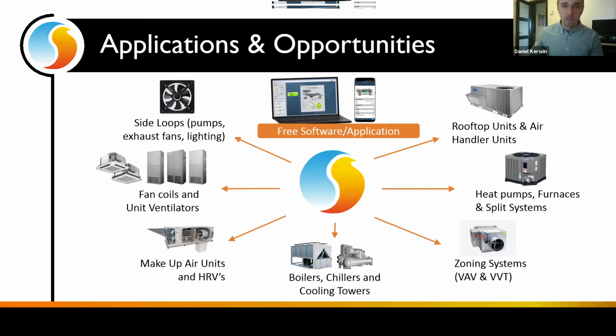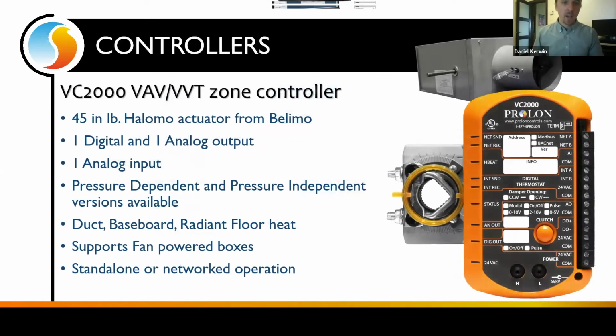So just to go over a few of these controllers. On the zoning side of things, we have a VAV controller right here, which has an embedded Belimo actuator on it, which is good for 45 inch-pounds, which is good for most dampers which we find. We have different models, whether it's a pressure-dependent model or pressure-independent model. And we have a variety of different outputs, which can allow us to control any kind of peripherals, such as reheat coils, baseboards, zone valves, if ever we have a fan-powered box application as well. So no matter what the application is, we can usually take care of it with this controller right here.